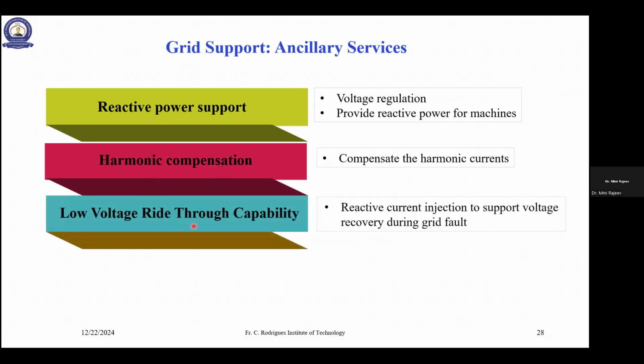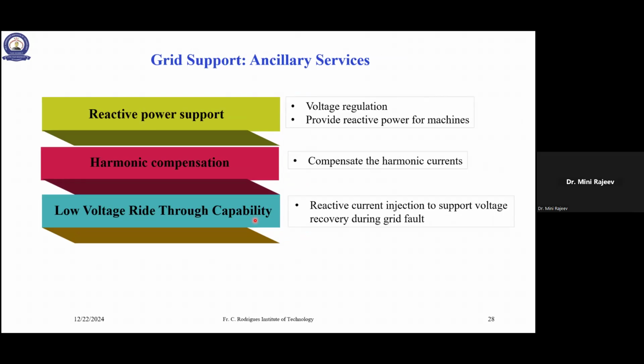Then low voltage ride-through capability. For small voltage sags and the like, the inverter can still remain connected to the grid and provide reactive power support. That is what we mean by low voltage ride-through capability. The inverter will remain connected and can provide reactive power support. It can also regulate frequency by active power control.